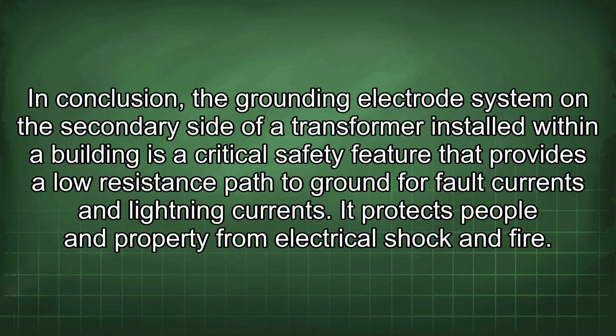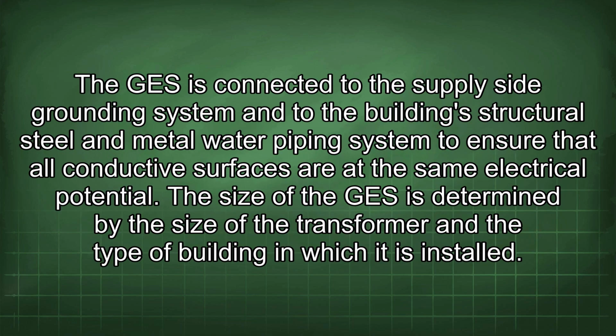In conclusion, the grounding electrode system on the secondary side of a transformer installed within a building is a critical safety feature that provides a low-resistance path to ground for fault currents and lightning currents. It protects people and property from electrical shock and fire. The GES is connected to the supply-side grounding system and to the building's structural steel and metal water piping system to ensure that all conductive surfaces are at the same electrical potential.